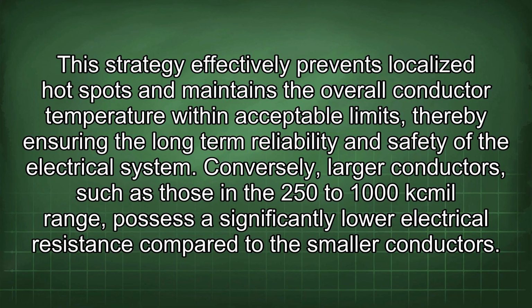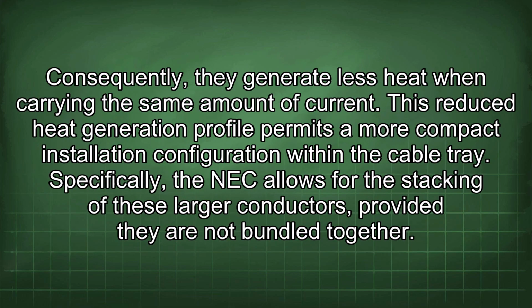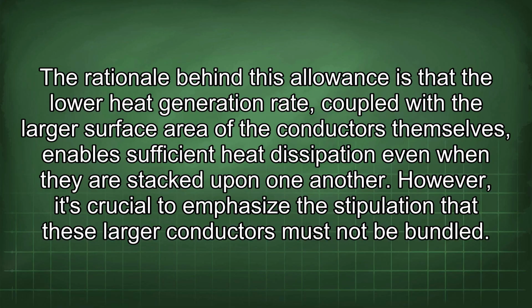Conversely, larger conductors, such as those in the 250 to 1000 kcmil range, possess a significantly lower electrical resistance compared to the smaller conductors. Consequently, they generate less heat when carrying the same amount of current. This reduced heat generation profile permits a more compact installation configuration within the cable tray. Specifically, the NEC allows for the stacking of these larger conductors, provided they are not bundled together. The rationale behind this allowance is that the lower heat generation rate, coupled with the larger surface area of the conductors themselves, enables sufficient heat dissipation even when they are stacked upon one another.